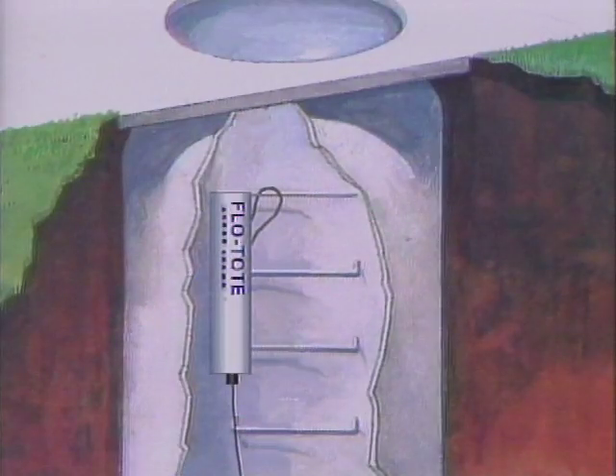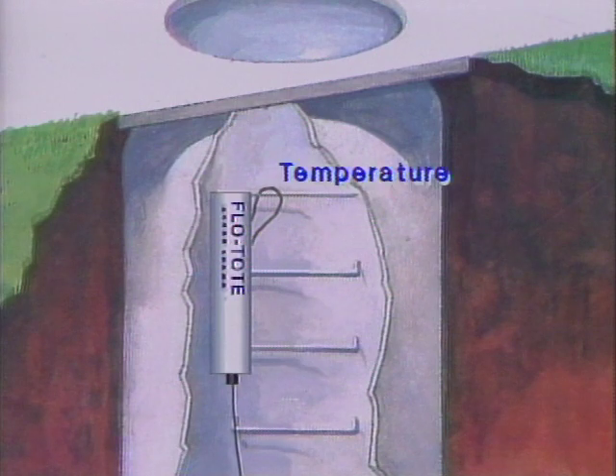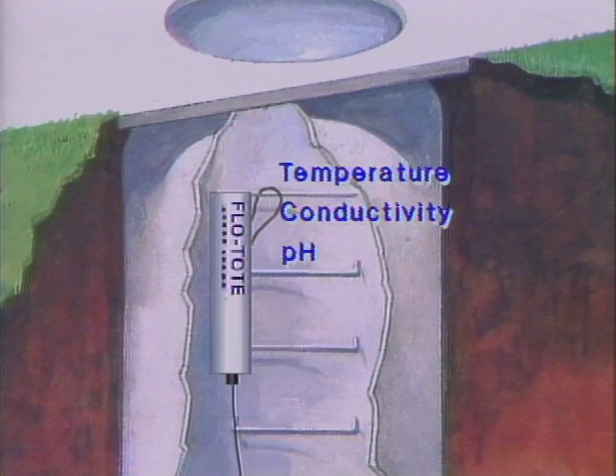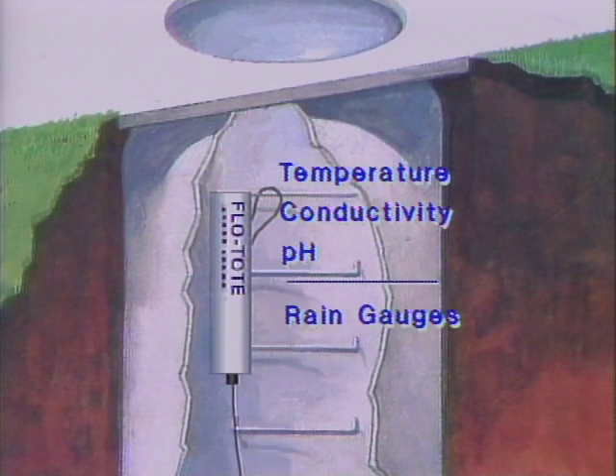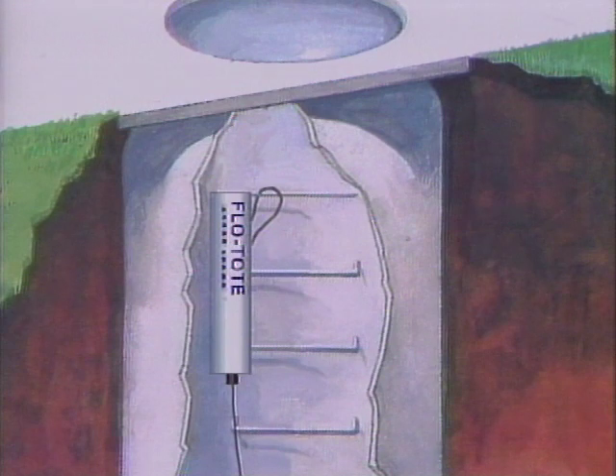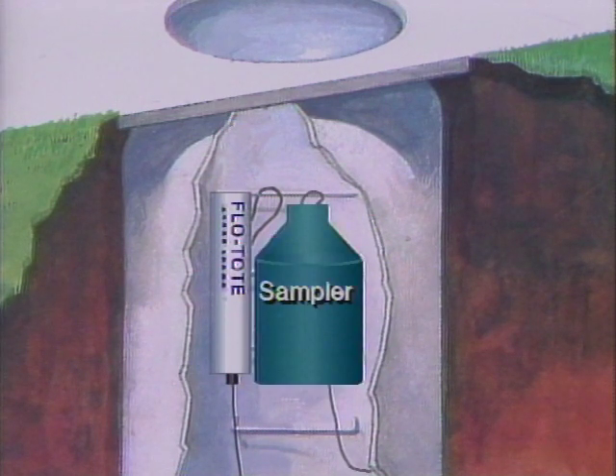An enhanced unit is also available with multiple input channels to log additional engineering data from analog sensors, such as temperature, conductivity, and pH, as well as keeping track of contact closures from devices such as rain gauges. The unit is also available with a contact closure that allows samplers to be triggered at a rate proportional to flow.